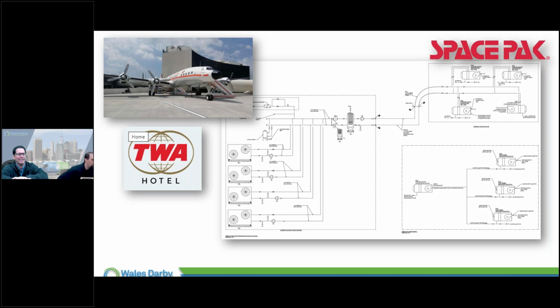How do you switch from heating to cooling? So that could basically be your demand command, or your thermostat. All of our heat pumps have a nice control strategy, very simple - we have two basically dry contacts we're sending out. One of them is on-off, to tell the machine to turn on and off. The other one is to turn the reversing valve in the direction we need.